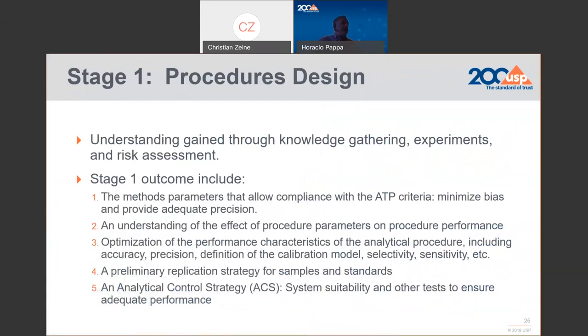Stage 1 is procedure design, the method development stage. Here we define what are the method parameters that allow compliance with the ATP criteria—minimizing bias and providing adequate precision. We understand the effects of procedure parameters on procedure performance, mainly through robustness. We optimize performance characteristics including accuracy, precision, calibration, and selectivity/sensitivity. Finally, we establish a preliminary replication strategy for samples and standards—something not usually included in the traditional approach—and we define the analytical control strategy, which includes system suitability parameters and other tests that will assure adequate performance.